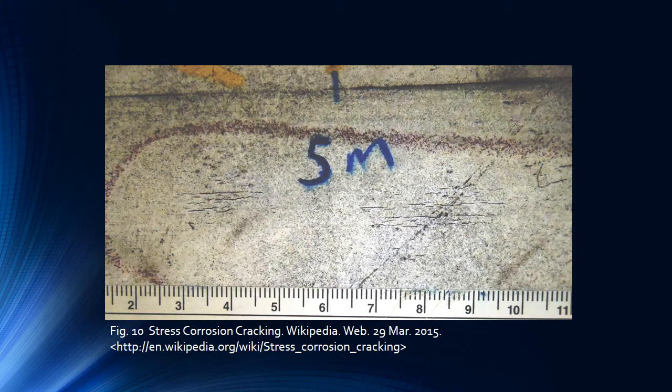Here is an example of a couple of clusters of stress corrosion cracks. This image utilizes magnetic particle inspection for clarity of the image.